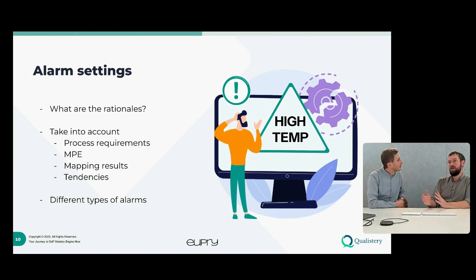We're also discussing the concept of alarm fatigue. If you get a lot of false alarms, it tends to tire people out and means you don't react on alarms. Those human factors have to be taken into account when tuning your alarm system so that it's not over-alarming.